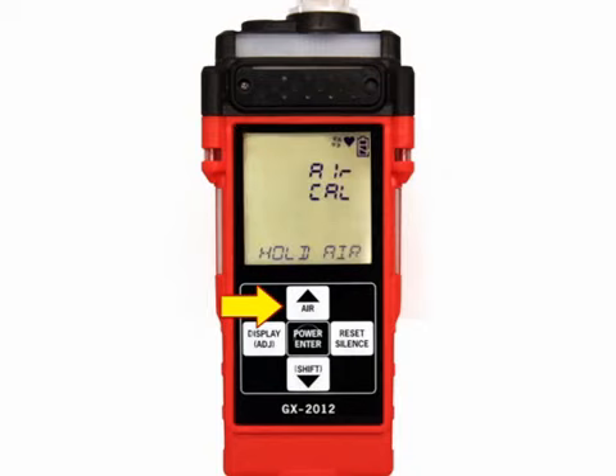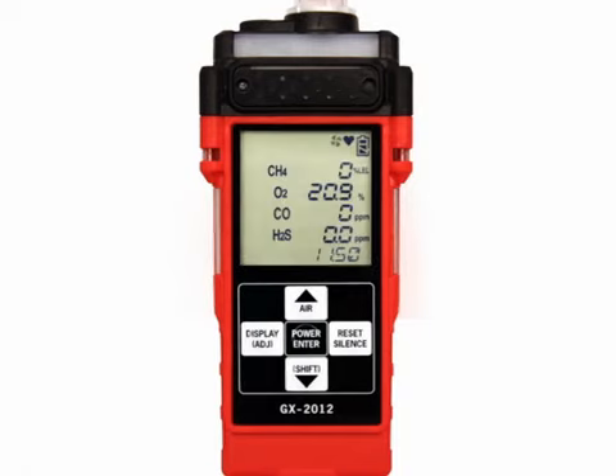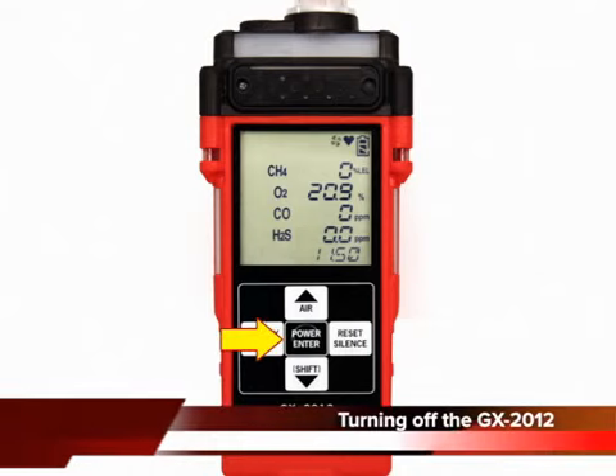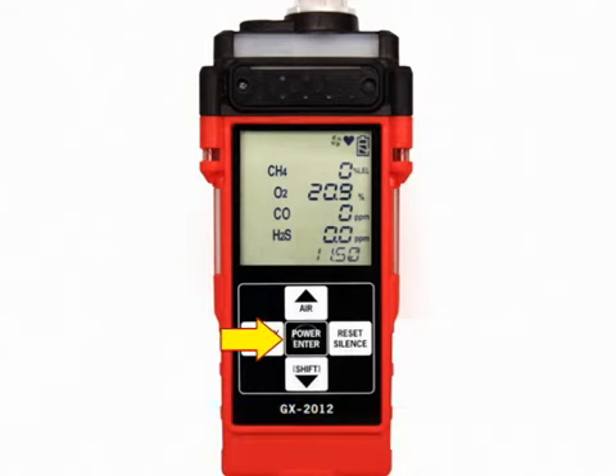On the display, you will see the message, Air Cal Hold Air, which is a prompt for you to continue pressing the air button. After a few seconds, the display will read Adjust Release, prompting you to release the air button. The unit will take a few seconds to adjust the fresh air readings, then return to the normal operating screen. Press and hold the Power Enter button for about 3 seconds to turn off the unit.